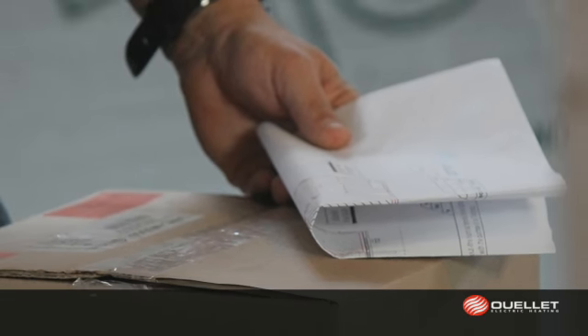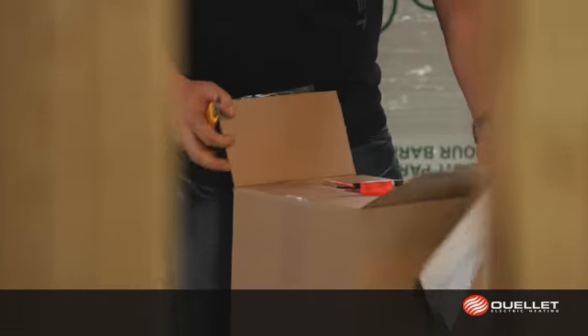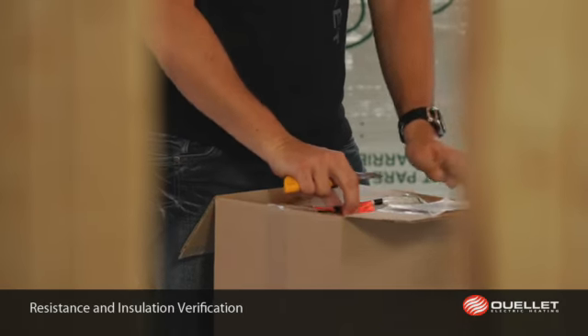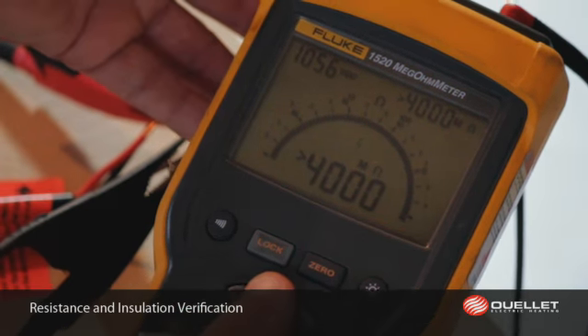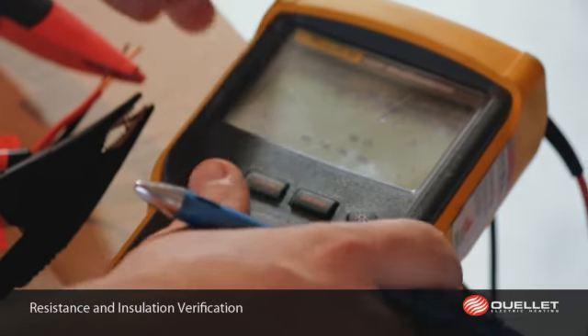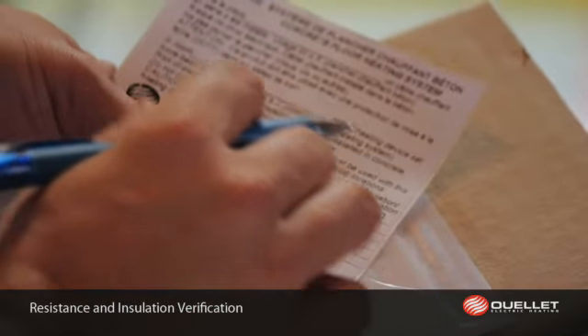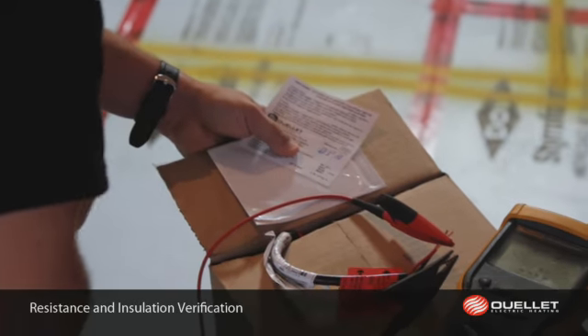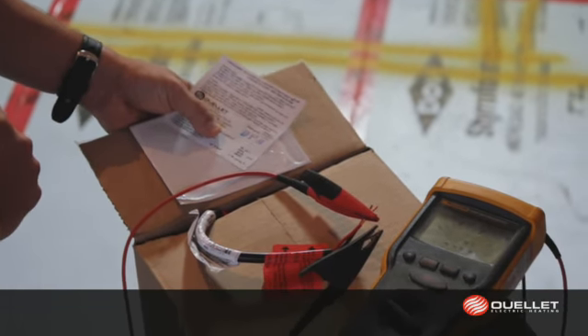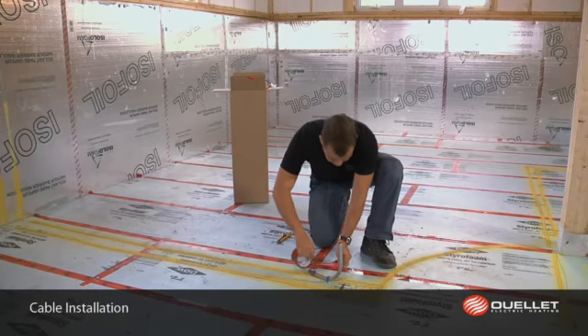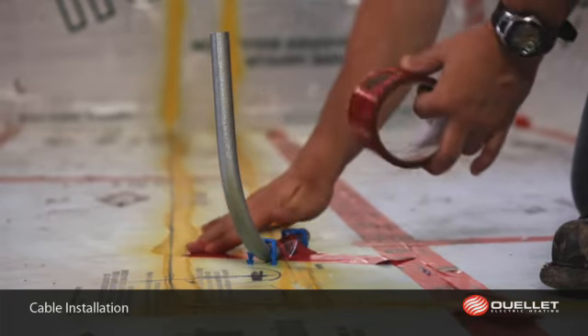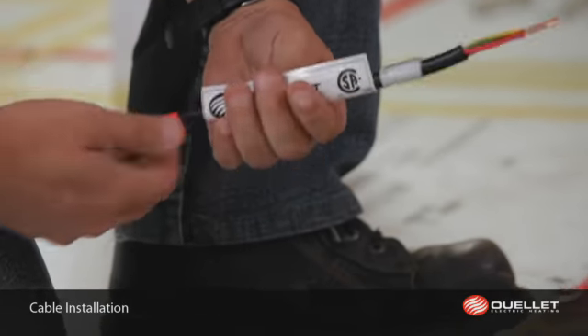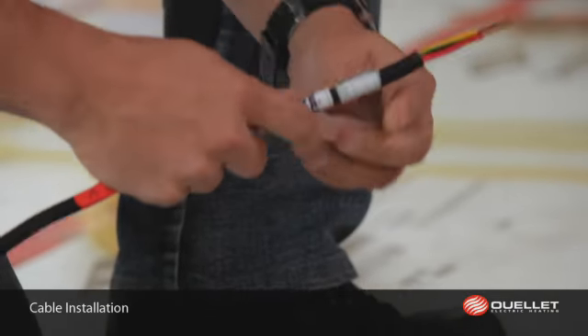For warranty purposes, a first measurement must be taken to ensure the cable's integrity before breaking the security seal. Check the resistance using a multimeter and cable insulation using a megohmmeter. Write down the values on the control sheet found in a plastic envelope. Wrap the label around the non-heating section of the cable.